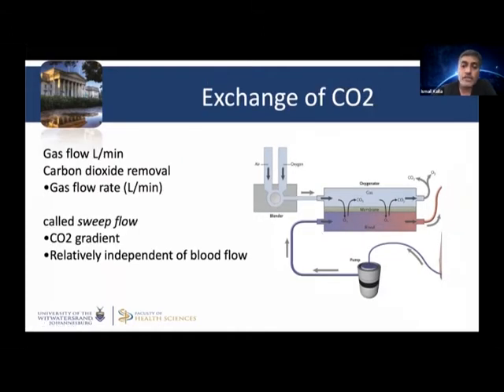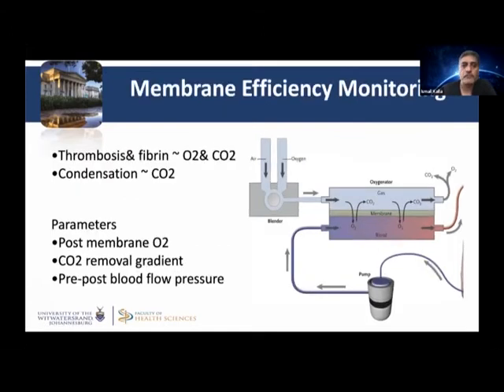In terms of carbon dioxide removal, the two main aspects that determine the amount of CO2 removal within the ECMO circuit are, one, not necessarily blood flow. You can have very minimal blood flows. That's why we talk about ECCO2R with even 100, 150 mils of blood per minute. But the membrane, so the efficacy of the membrane, the porosity of the membrane and the function of the membrane with time, and then the flow rate of gas within this chamber. So the flow rate of the dialysate gas, or the dialysate fluid, as you would be more familiar with in terms of speaking as a nephrologist.